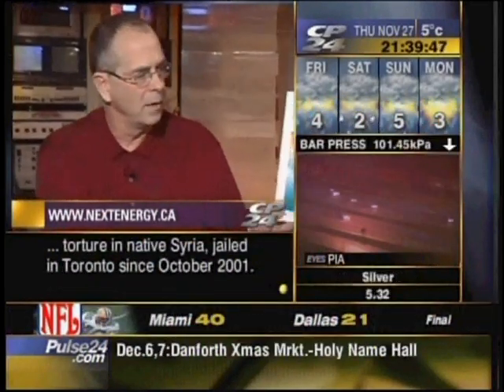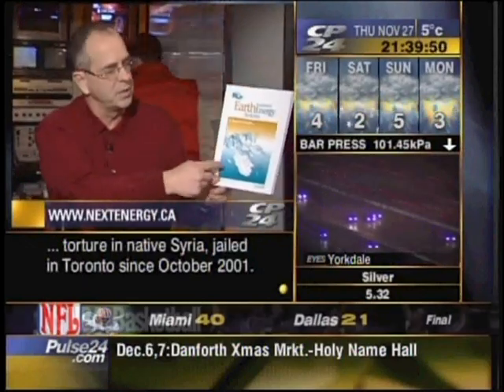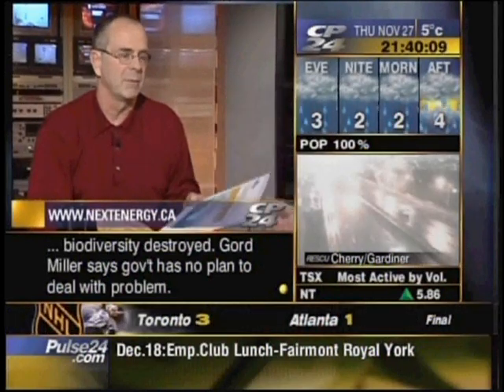Is there a minimum size yard you need? Not really. We do mostly rural residential because we've got lots of land area and we can put it in horizontally. There's a picture here of a ground loop system, a schematic of piping that's put in trenches in the ground. You can also put them in vertically, straight down. That's more expensive because you have to drill, but once the volume of installations goes up, we'll see the verticals take over. So you can basically put it in a driveway, or an ordinary yard.